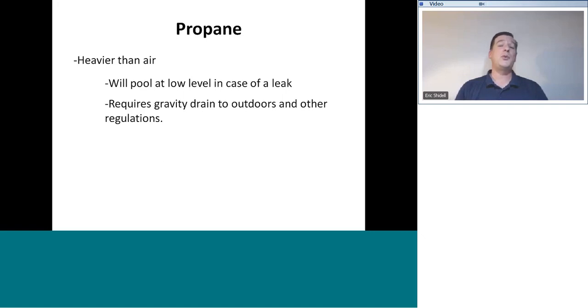That gravity drain to outdoors is going to look just like a floor drain, just like a wastewater drain. But in fact, it'll be a 2-inch PVC pipe that will go from the floor, under the floor, sloping downward to the outdoors, and where that propane will naturally flow out and go to the outside. But hey, what if you have a gas appliance in a basement or a crawl space that's below grade? You're not going to be able to get propane to slide down the drain. It's not going to go up to the outside, and that's correct.